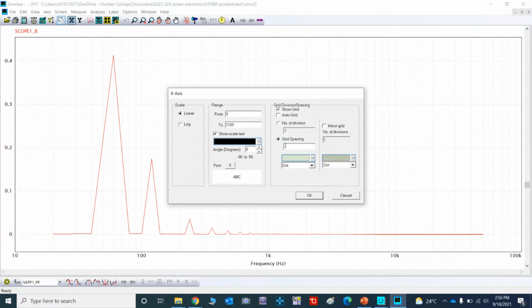Okay, and you can see we now have all the harmonics, all the components of the harmonics. The 60 hertz component, the fundamental, has an amplitude of around 0.41 ampere. So this is the amplitude, or the peak, of the fundamental. This is the peak of the second harmonic, and this is the peak of the fourth harmonic. 240 is 4 times 60, so this is the fourth harmonic, and this is the sixth harmonic. We don't have the third harmonic and fifth harmonic in this waveform.